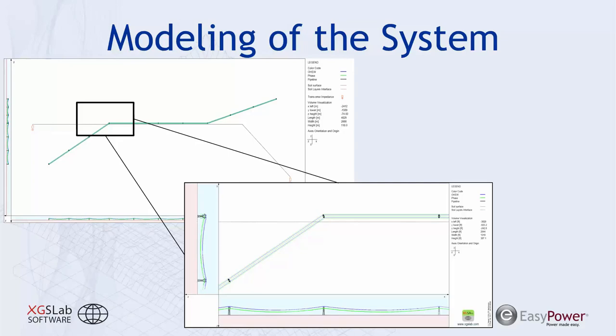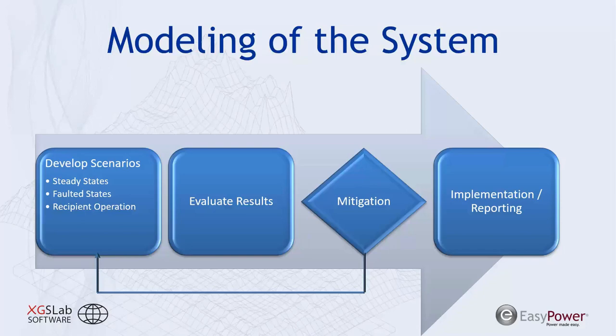When you have modeling software, it makes the process much quicker because it allows you to develop your scenarios, such as your steady state analysis cases, your faulted states, and any recipient operational practices, and run those through the software to determine what your induced coupled voltages are and determine if those are meeting your compliance limits or exceeding your compliance limits.